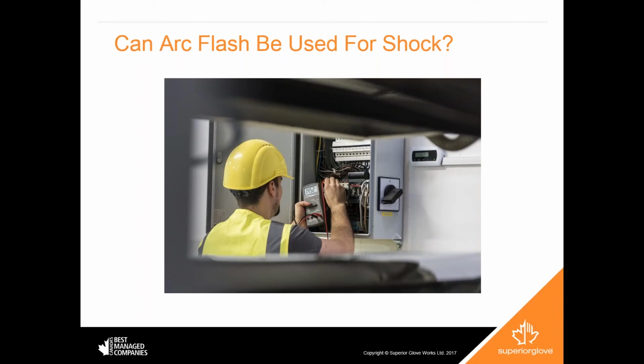It's not something, when you get into that area, you are really in an extreme danger zone. But let's throw an example out of saying that you're going up to throw a breaker switch or pull a main switch on a box. In that case, you're going to be standing within that zone, and having that glove on versus not having that glove on can mean, as we said earlier, you've got a 50% chance, depending on the voltage and the cal rating of an arc flash at that time, as to whether you walk away without a severe second-degree burn or worse, or hopefully we keep the burn and the incident down to that level. So wearing something like that at that point is certainly better than not having anything on at all.